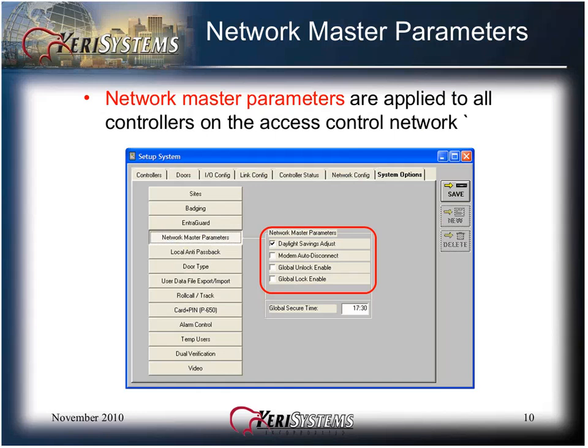Network master parameters are applied to all the controllers on the access control network. The Daylight Savings Adjust is on by default. It allows automatic daylight savings time adjustments at controllers per U.S. standards. Turn this option off if the controller is installed in a geographic location that does not observe daylight savings time.